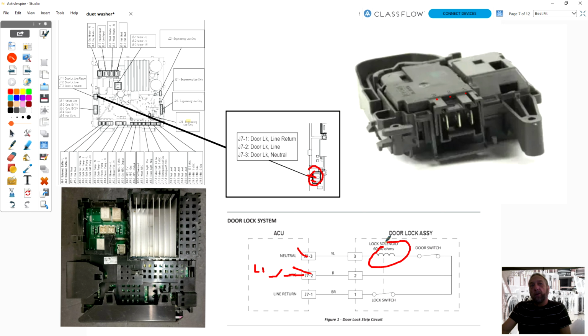My lock solenoid is not engaging. I don't hear it, and I have 120 volts, so my lock is bad. I've already ohmed it out, and I know my door switch is good and my solenoid has good resistance. It's not working, and I've got power.